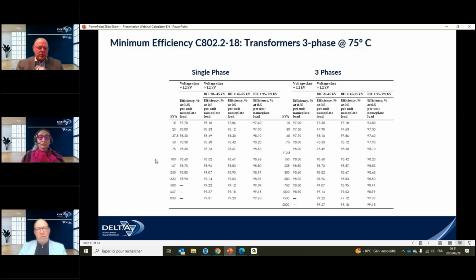So I was explaining earlier that depending on your kVA and your voltage class, the efficiency level will be different. This is how the CSA C802 standard is built. They provide us with tables. Depending on your kVA, voltage class and your load level, you have to meet that efficiency level. So we calculate efficiency based on those requirements, and if we comply, we're good. We can build and manufacture those transformers.